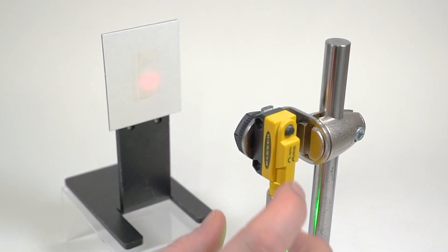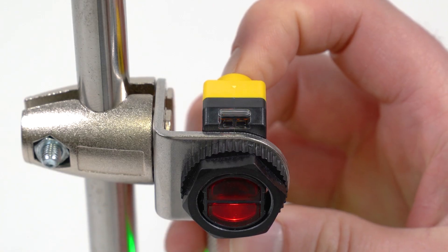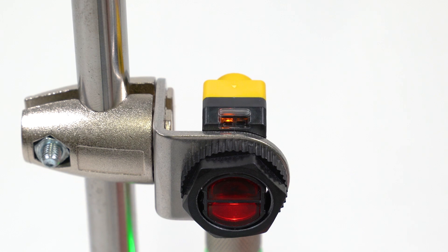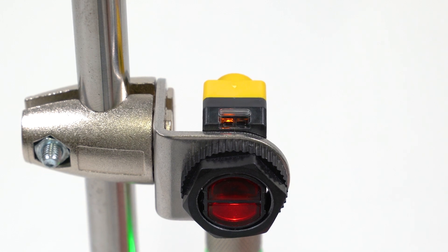To teach the sensor with the light set mode, press and hold the push button for two to four seconds until the green power LED turns off and the amber output LED flashes once per second.